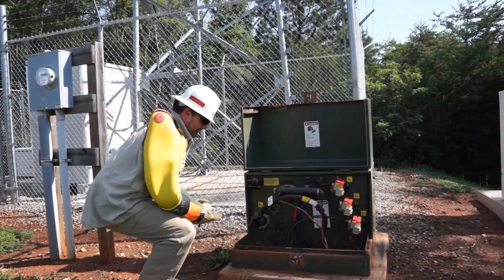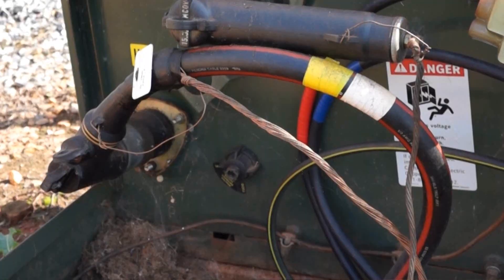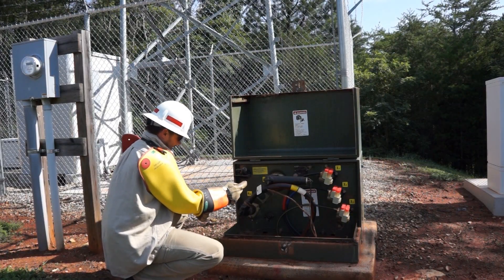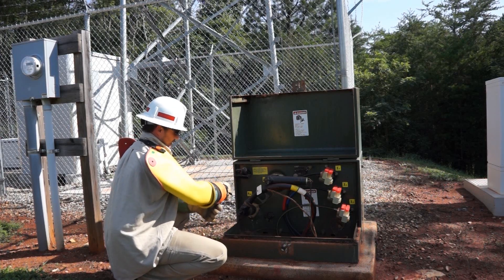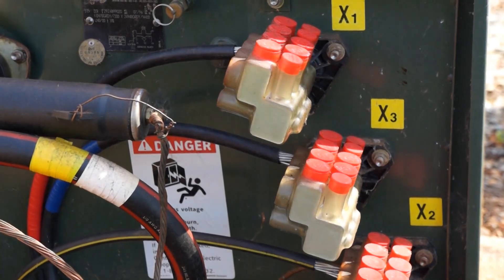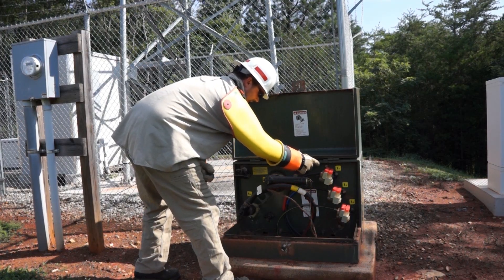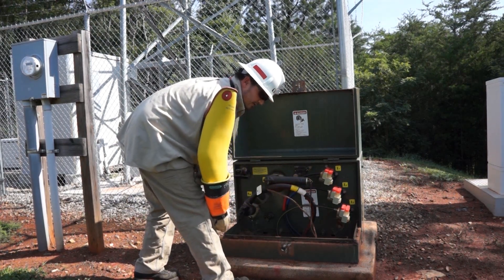The way this works is our primary voltage enters through this cable right here. On this cable is 14,400 volts. It enters through this H1A bushing, goes through the transformer, through the windings, comes out on this side which are the X bars, and from the X bars it goes through connection points. It leaves our cable, goes to the meter, and serves the customer with 120-240 voltage.